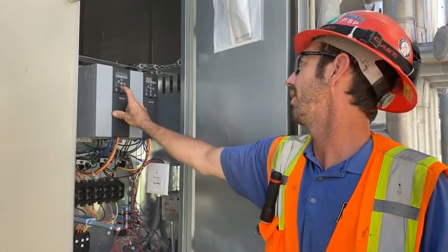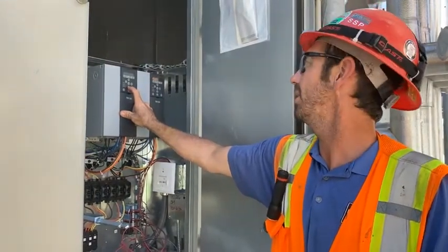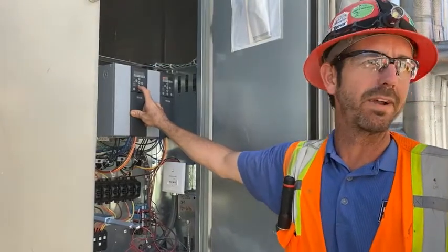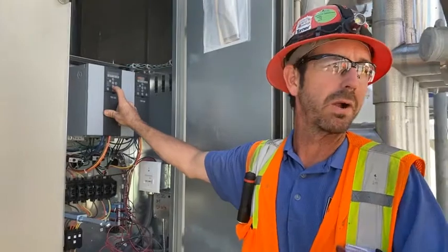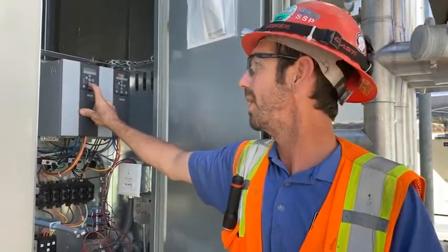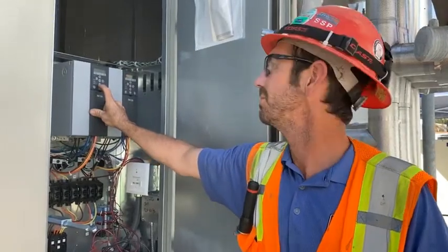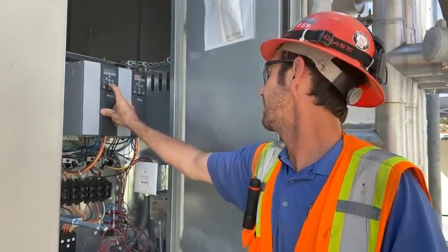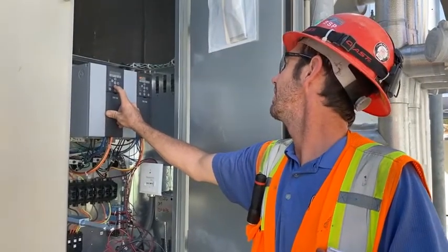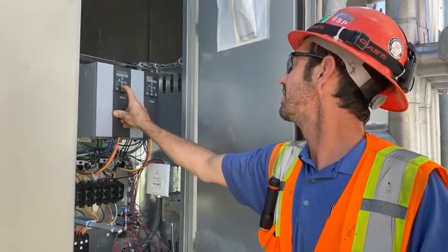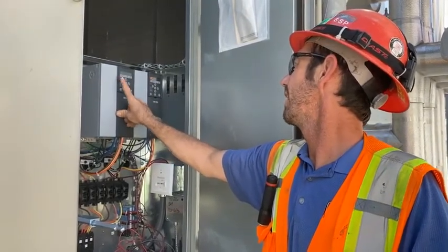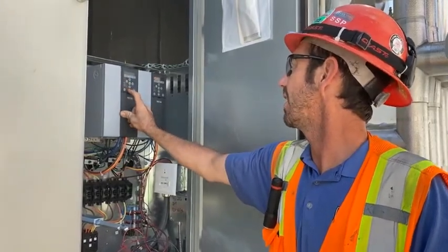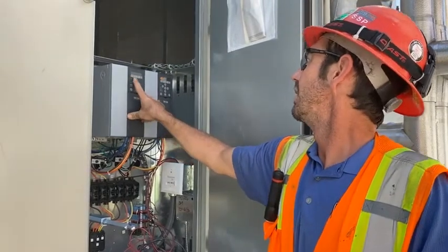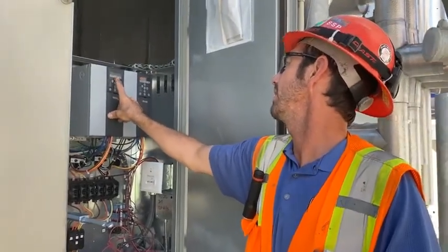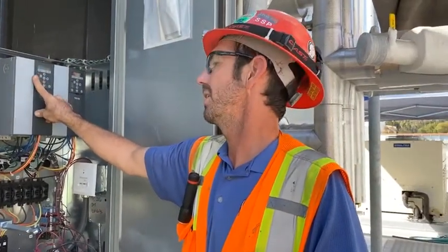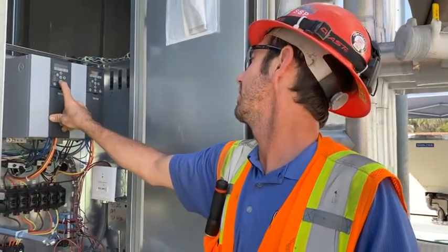So if we use the down and up arrows, we're going to scroll through the different options that are available. I press down, now we see horsepower. The used horsepower right now is 0 because the unit's off, okay? But if it was running, it would give you a horsepower reading of what the motor is drawing from the VFD. That can change depending on the speed of the fan, okay? I don't see a reference on this one. It's at 0. This would be a speed signal. Amperage reading, we're at 0 because the unit's off, and then a Hertz reading. So we're at 0 again because it's off. That's the status menu. If you press menu, you'll go to a quick menu. There's a setup wizard. We shouldn't need to make any changes there. We're not using a closed loop setup.